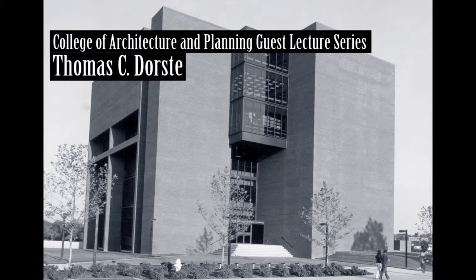It turned out that the piping system in the building was adequate storage for the hot water. In other words, the building was large enough that the piping system would store enough water that the interior portions of the building, which required cooling, supply enough hot water to the exterior that only under the most severe conditions does the boiler kick in at all. Okay. As near as we can tell at this point in time, total energy in that building, and I'm almost afraid to say this because I think there's something wrong with it, for 6 months was 17 cents a square foot, which would be 34 cents a square foot per year, but it's only partially occupied, and I don't know what that does to the figures.